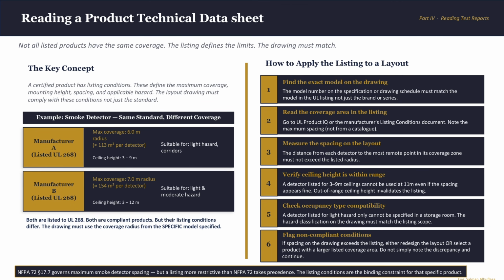And this one trips up even experienced engineers. A listing is not general approval of a product. It is a permission with boundaries, and those boundaries are the listing conditions. Let's take an example to understand that further. Two smoke detectors, manufacturer A, manufacturer B, both listed to UL 268. Same standard, both compliant products. But manufacturer A covers a maximum radius of 6 meters and works for ceiling heights of 3 to 9 meters only. Manufacturer B covers a 7 meter radius and works for ceiling heights from 3 to 12 meters. Same standard, but different boundaries.